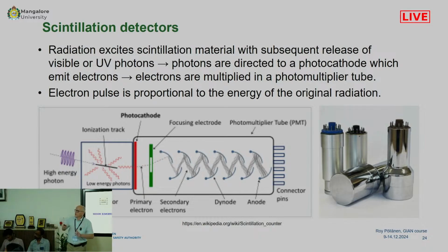And then there are scintillation detectors, which operate so that radiation coming here or from the bottom generates photons inside here.